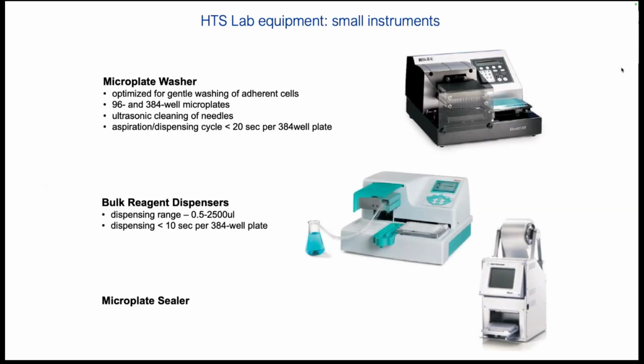This is done with plate washers. The washing is done with these machines that aspirate the content of the well and then dispense the washing solution. You can define different parameters, speed, height, and so on. What we typically do is leave some volume at the end of the well so that it cushions the liquid that is coming in. By doing this, you can get a good compromise between detachment and washing. There are some problematic cells, but there's usually a good alternative.